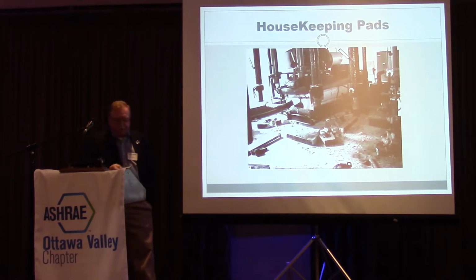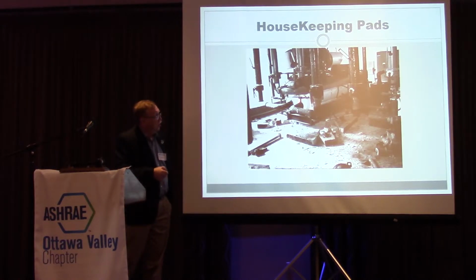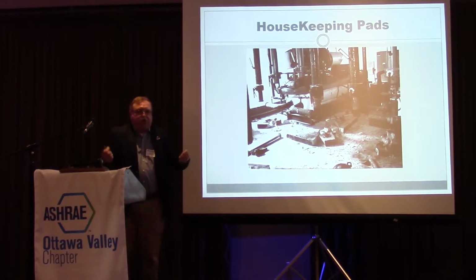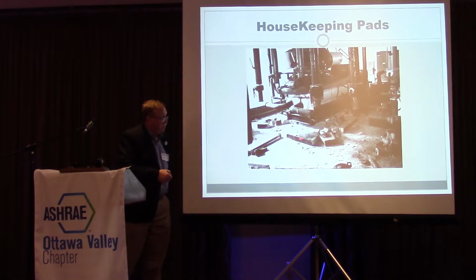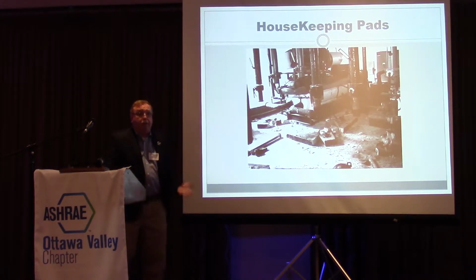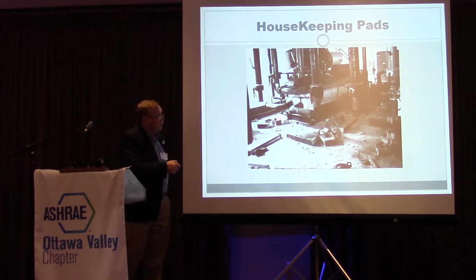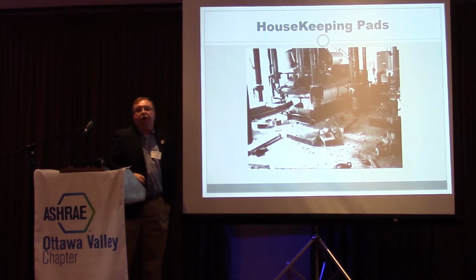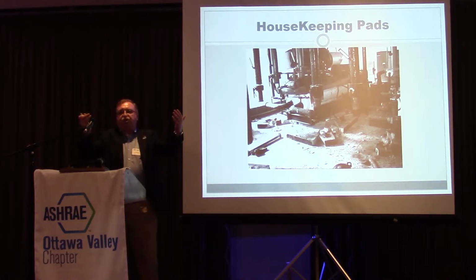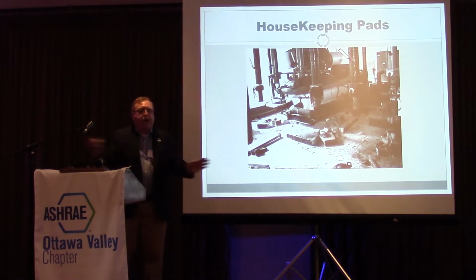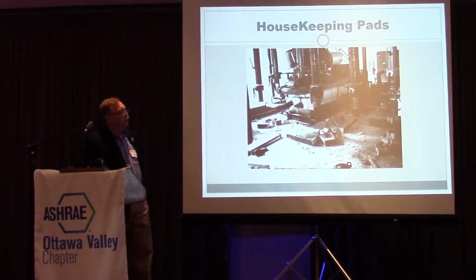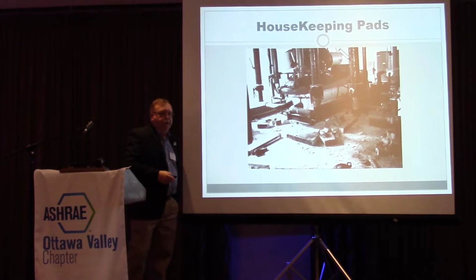This floor saw a 1.1 vertical G input. So the assumption is the earthquake came, the equipment got pushed up in the air, and since it was not attached to the structural slab but attached through these seismic restraints to the chiller itself, it went up with the chiller, came back down, and shattered like a pane of glass, going every direction humanly possible.